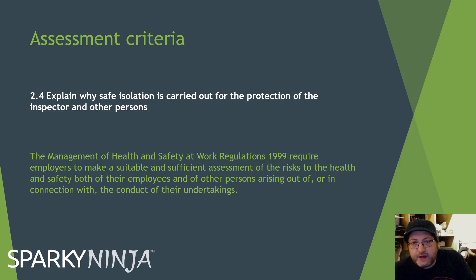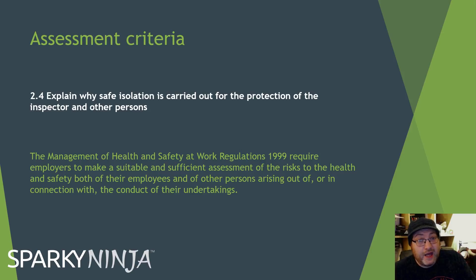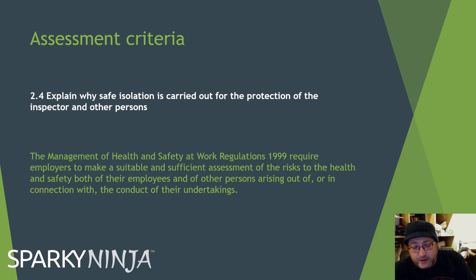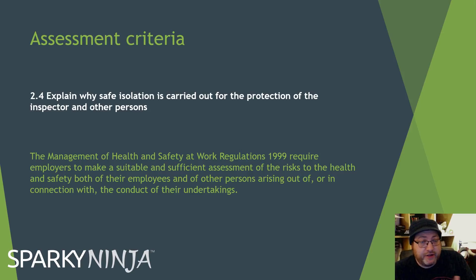For other persons, we've got to make sure that persons working adjacent to where we're working are safe — it could be other contractors on the plant. You may have a multi-lock hasp where you and someone working on mechanical, other electrical, or other services who are also at risk need to also control the isolation point. The isolation procedure is carried out for a number of reasons and for a number of persons.